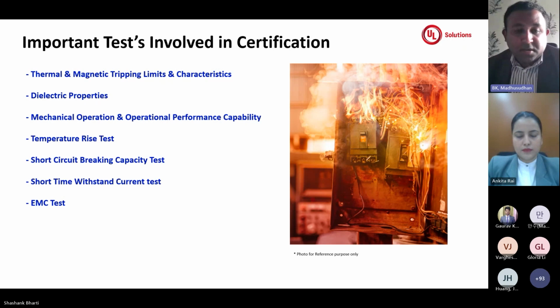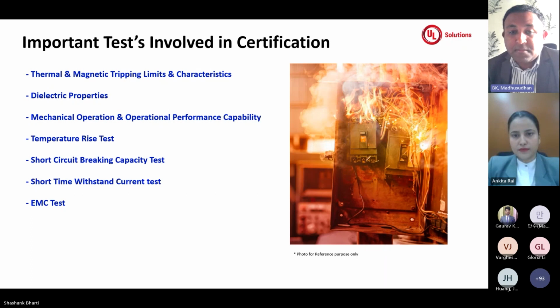Next is the temperature rise. Basically, this test is conducted on the higher ratings of the breakers to ensure that the complete range falls within the purview criteria of the standard. Again, the standard gives reference temperatures for the materials you are going to use on the terminals and other parts. Based on those declarations from manufacturers, testing will be conducted and different temperatures measured. The standard gives clear guidelines on whether you are using copper, aluminum, or a combination of other alloys. There are different temperature limits for each alloy and material. The temperature measured should be within the limit, and if it crosses, that will be a failure. If it is within the limit, then that can be considered acceptable.